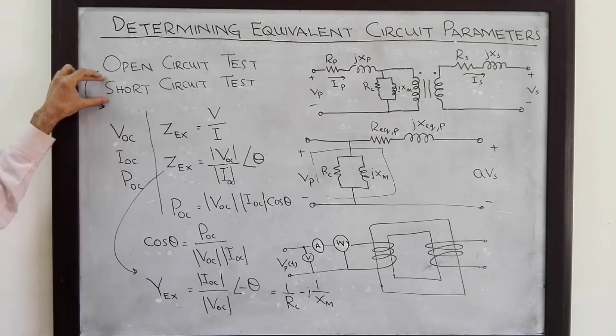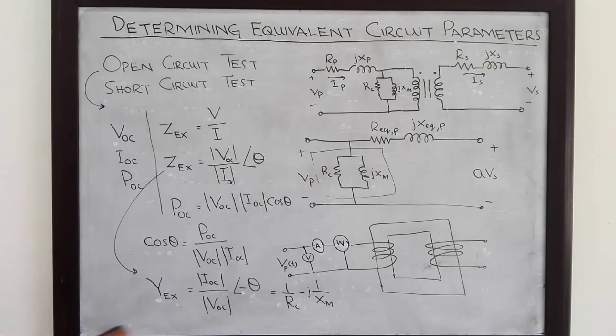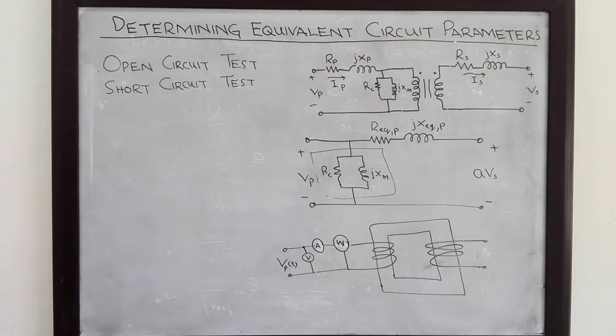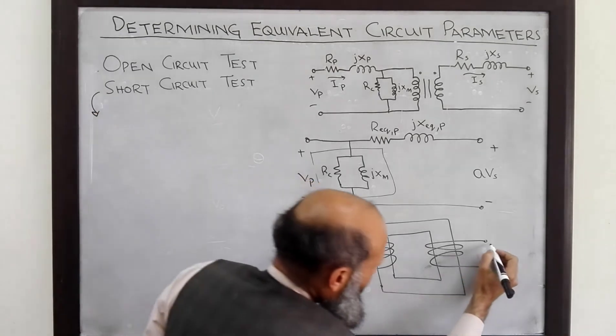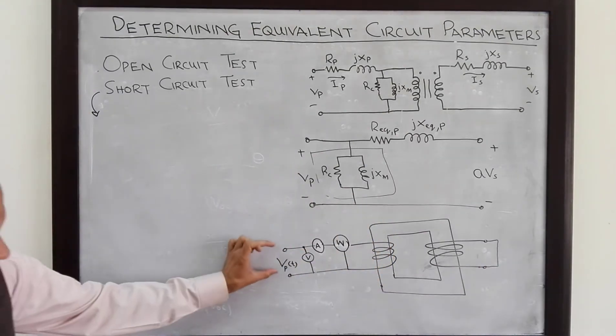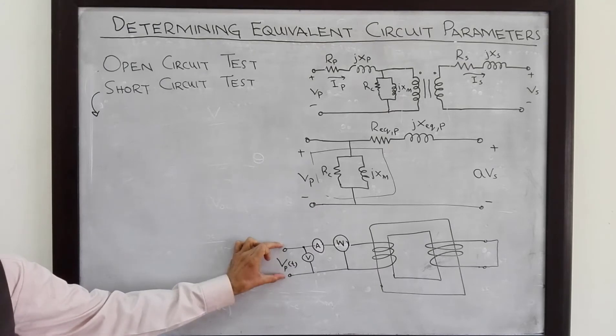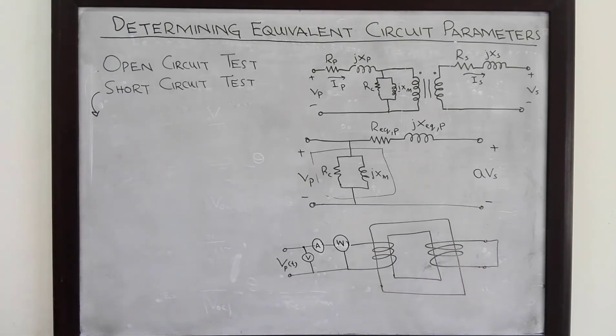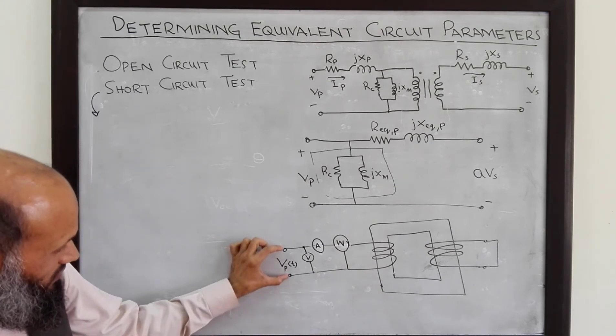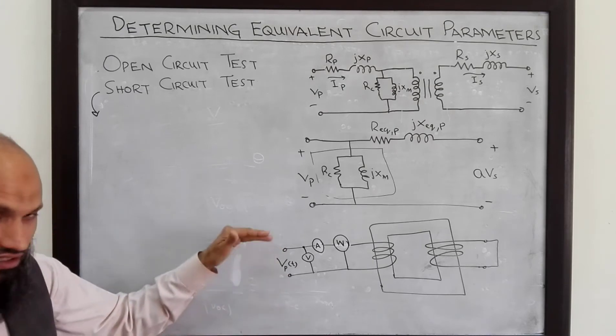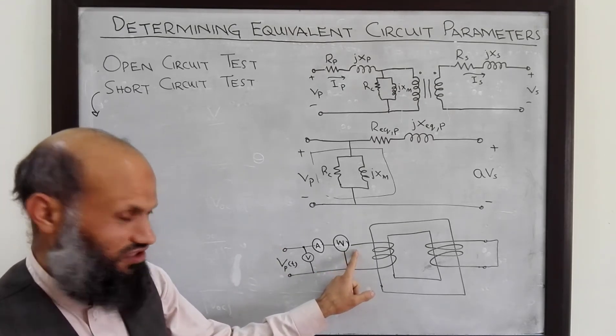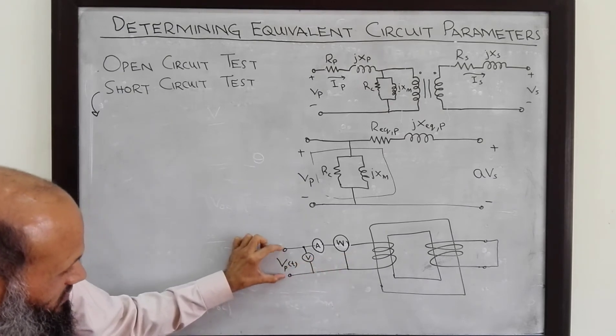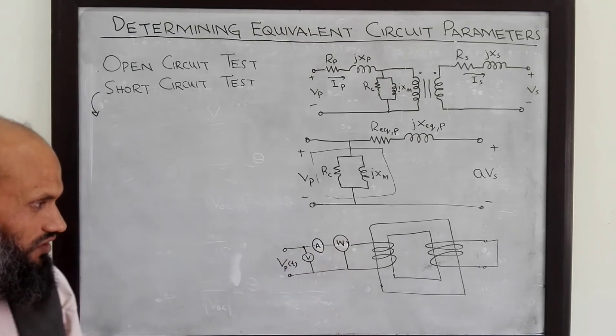The second test performed is the short circuit test. For the short circuit test, we short the secondary. However, we do not apply the rated voltage, because if we apply rated voltage, excessive current will flow through the transformer since the secondary is short circuited, and this may damage the transformer. So we apply low voltages and increase gradually until the rated current flows in the transformer.